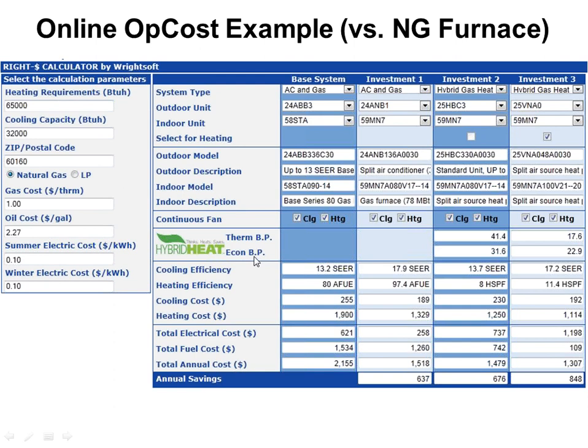It calculates that for us, so we don't have to do it on the chart. So that first heat pump, the entry-level one, says the thermal breakpoint is 41 degrees. That means when it gets below 41 degrees outside, that heat pump will not be able to generate enough heat to heat the space. Economically, it's saying the changeover point is 31 degrees. So when it gets below 31 degrees, at these gas and electric costs, it'll become cheaper to run the gas furnace instead of the electric heat pump.